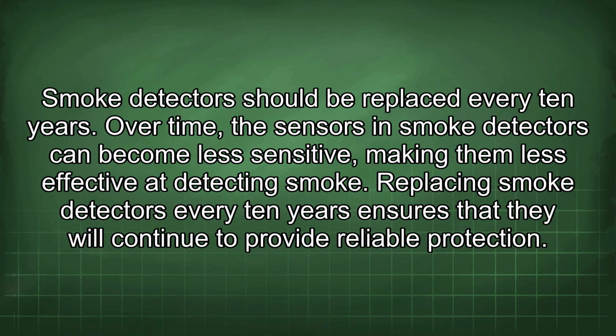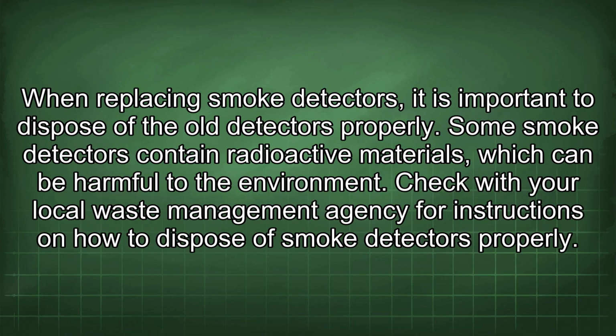Smoke detectors should be replaced every 10 years. Over time, the sensors in smoke detectors can become less sensitive, making them less effective at detecting smoke. Replacing smoke detectors every 10 years ensures that they will continue to provide reliable protection. When replacing smoke detectors, it is important to dispose of the old detectors properly. Some smoke detectors contain radioactive materials which can be harmful to the environment. Check with your local waste management agency for instructions on how to dispose of smoke detectors properly.